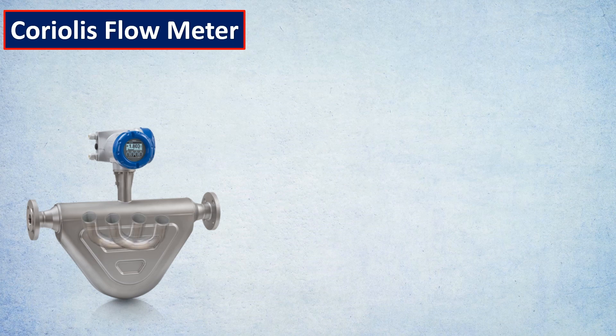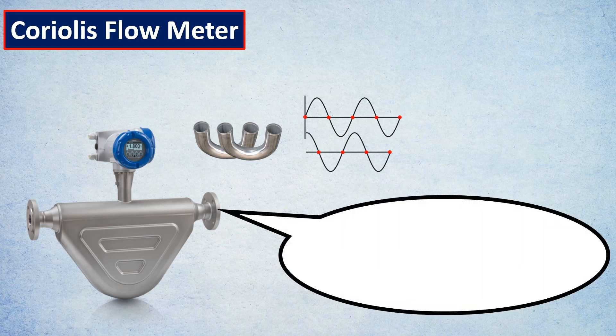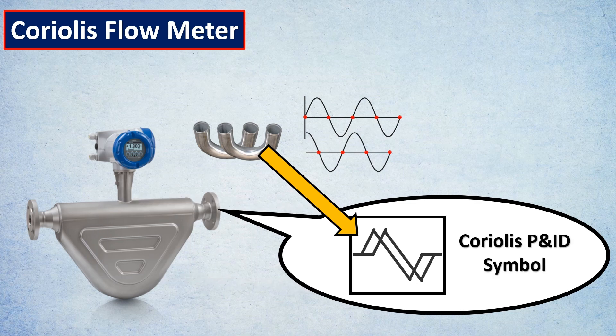For example, take Coriolis flow meter. It is basically two tubes vibrating together. The more out of phase they are, the higher is the flow. So engineers have done a smart thing. They have tried to mimic the tube, which is the most important part of a Coriolis flow meter, and here is the body of the meter. So this is the Coriolis P&ID symbol.